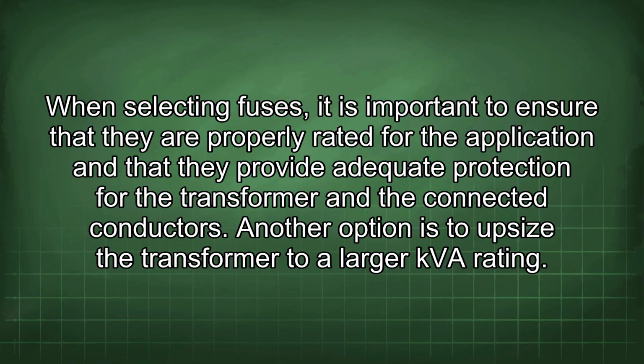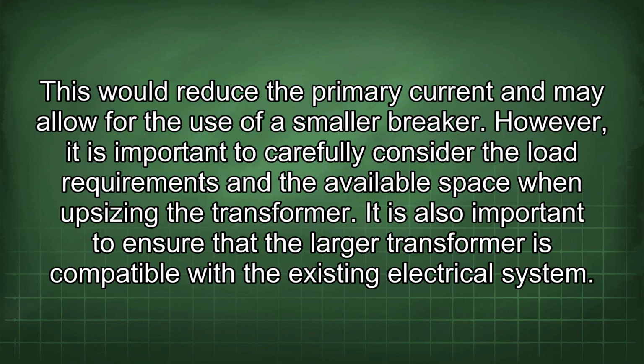Another option is to upsize the transformer to a larger kVA rating. This would reduce the primary current and may allow for the use of a smaller breaker. However, it is important to carefully consider the load requirements and the available space when upsizing the transformer. It is also important to ensure that the larger transformer is compatible with the existing electrical system.